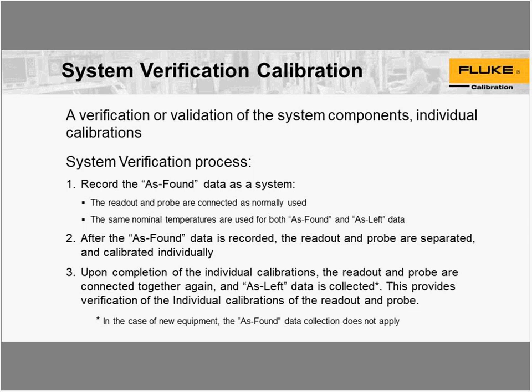So the way we would do that is we would record as found data as a system, both units connected, and then the as found data is taken. We would separate the two units and send the probe off to be calibrated by itself, and the readout also calibrated by itself. Upon completion of the individual calibrations, the equipment is turned back to my lab, and then I would take as left data on it. That should provide verification that yes, the probe calibration is valid, and so is the readout calibration.